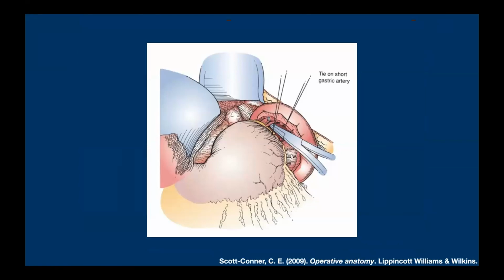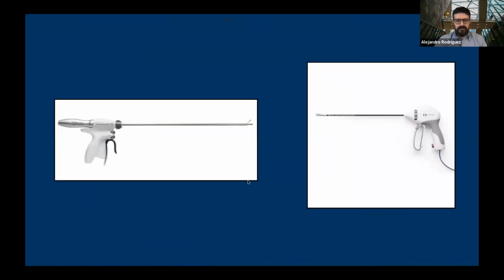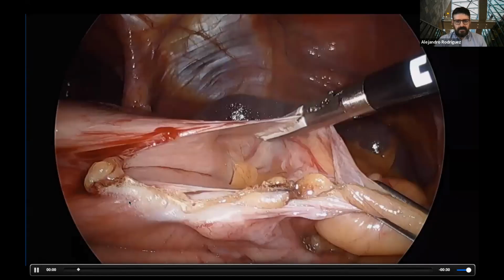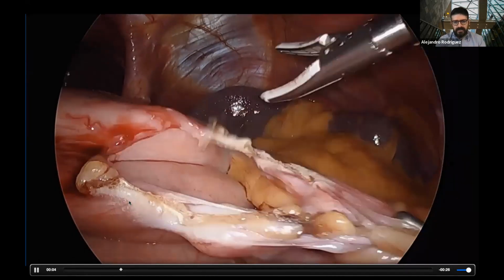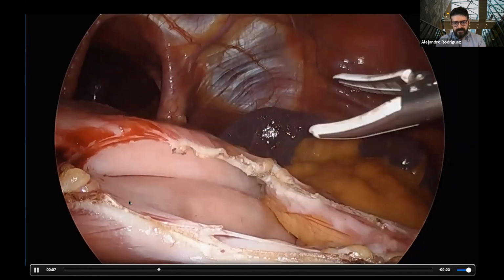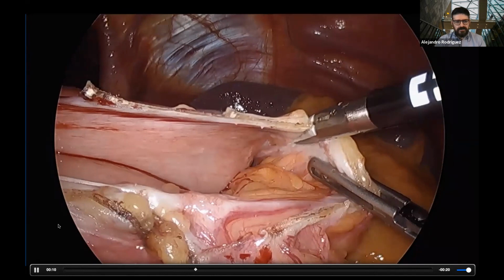Laparoscopic surgery necessitated an evolution of the technology. Both ultrasonic and bipolar technologies predate the laparoscopic revolution by a long time, but new devices were definitely implemented in response to laparoscopy. The most common ones are the harmonic or ultrasonic device, and the advanced bipolar, famously called the LigaSure device. So instead of ligate-cut, we just got cauterize-and-cut. This is an advanced bipolar device going through short gastrics.